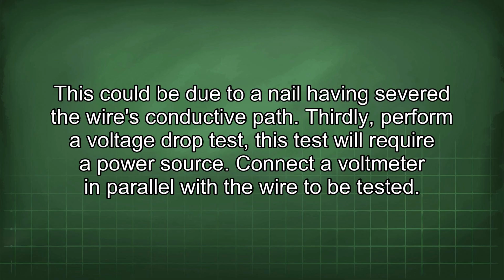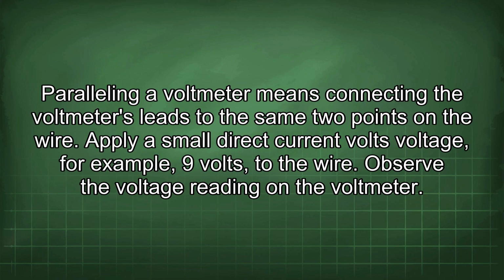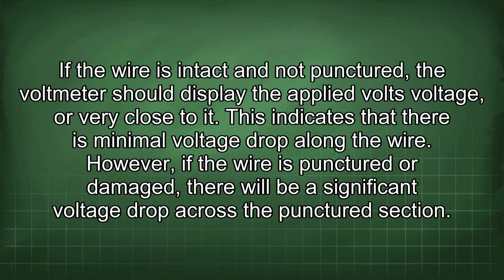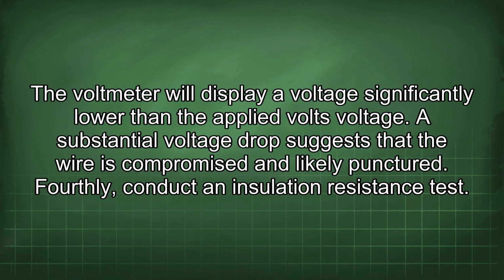Thirdly, perform a voltage drop test. This test will require a power source. Connect a voltmeter in parallel with the wire to be tested. Paralleling a voltmeter means connecting the voltmeter's leads to the same 2 points in the wire. Apply a small direct current voltage, for example, 9 volts, to the wire. Observe the voltage reading on the voltmeter. If the wire is intact and not punctured, the voltmeter should display the applied voltage, or very close to it. This indicates that there is minimal voltage drop along the wire. However, if the wire is punctured or damaged, there will be a significant voltage drop across the punctured section. The voltmeter will display a voltage significantly lower than the applied voltage. A substantial voltage drop suggests that the wire is compromised and likely punctured.